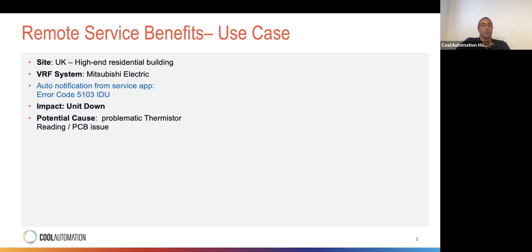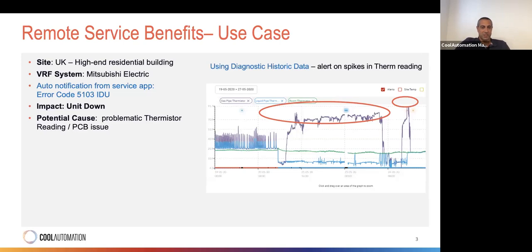In our case, we had the service app connected to the system, and we automatically got an alert. Once the technician got the alert, this is what he saw on his screen - a thermistor issue, the error code - but then he could go back in history and see how those thermistors behave. You can see very easily in the slide there's a spike in the thermistor behavior, and immediately you can see which thermistor is the problematic one and which ones are working properly.